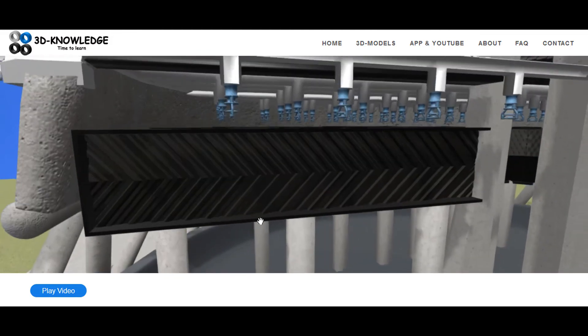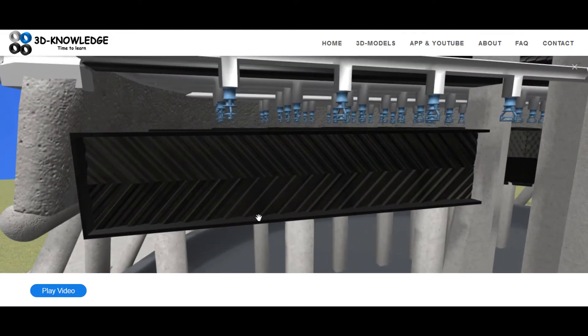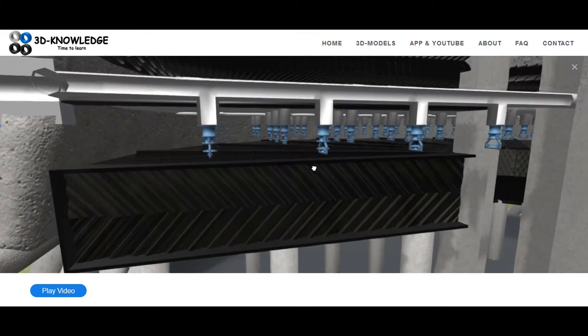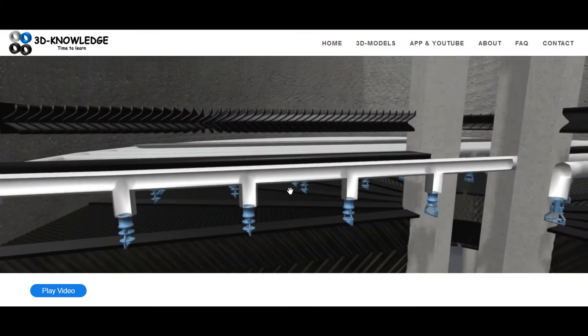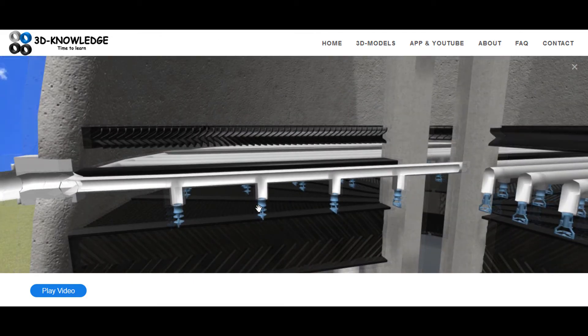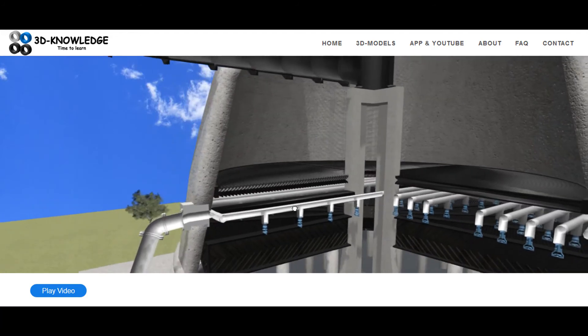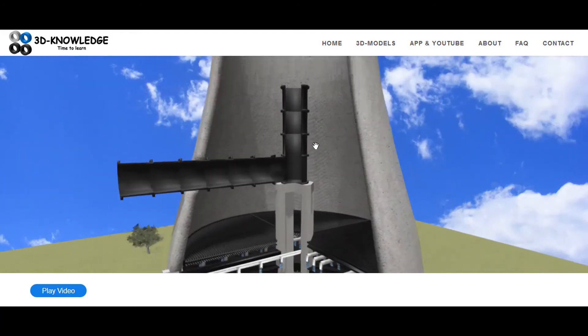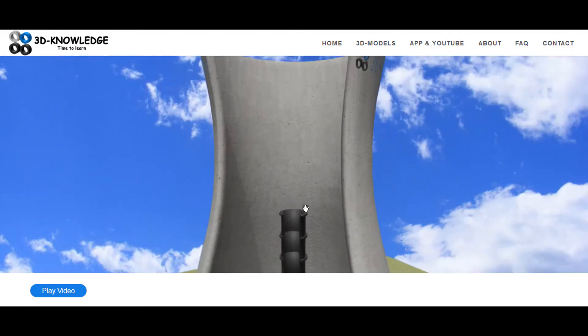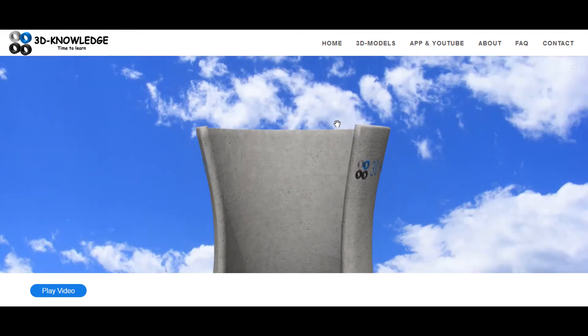The water dropped out and back into the reservoir, but the air itself — because it's been heated by the water — is going to rise. It is less dense than ambient air, and because it's less dense it's going to rise through the tower. The shape of the tower itself is going to accelerate that rise and it's going to be discharged out of the top of the tower. This is known as the stack effect.